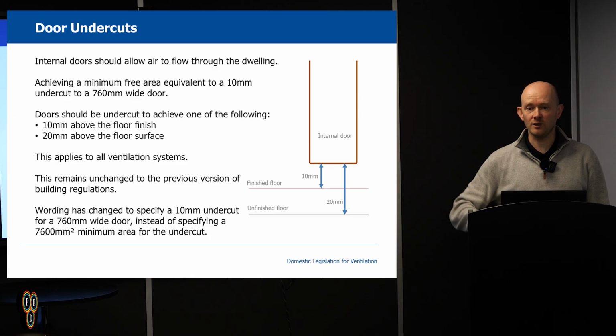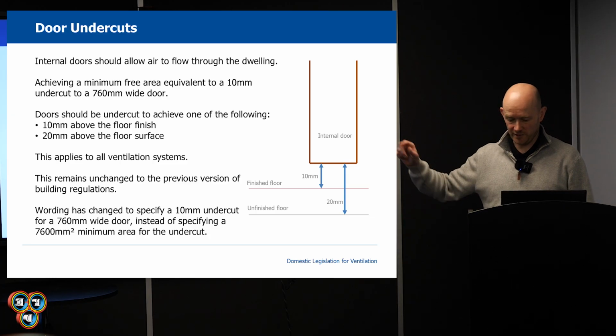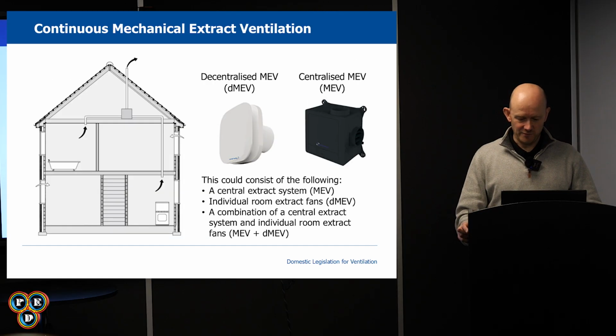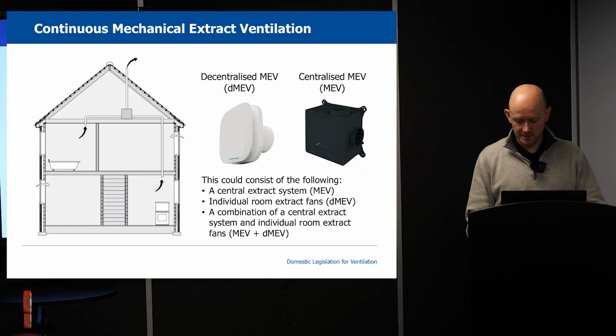To eliminate that, to allow the homeowner to shut every door, put 10 mil in. We move into the next type of ventilation system, which is probably more poignant at this moment in time. Continuous mechanical extract ventilation, which can be achieved through 2 different types of ventilation systems. A combination of such is a decentralised mechanical extract ventilation, DMEV, or a continuous mechanical extract, an MEV.